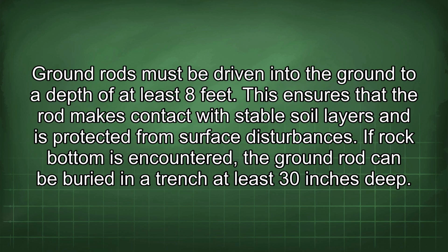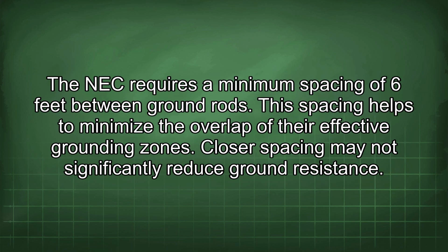Ground rods must be driven into the ground to a depth of at least 8 feet. This ensures that the rod makes contact with stable soil layers and is protected from surface disturbances. If rock bottom is encountered, the ground rod can be buried in a trench at least 30 inches deep. The NEC requires a minimum spacing of 6 feet between ground rods. This spacing helps to minimize the overlap of their effective grounding zones. Closer spacing may not significantly reduce ground resistance.